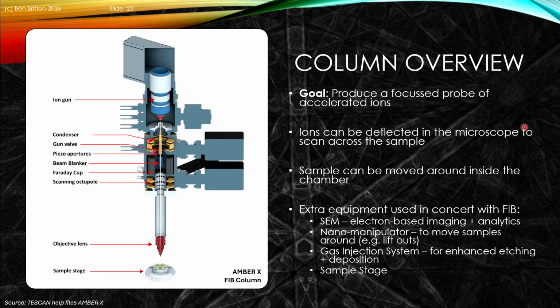Now, the sample itself is typically mounted on the surface of a carousel and stage, and so we might have, for instance, X, Y, Z, and R that enables us to move the sample around the chamber. So we can exchange from looking perhaps at our sample to then move over and shift to a handling grid that will enable us to pick up our nano or micron sized sample and put that in a secondary instrument.